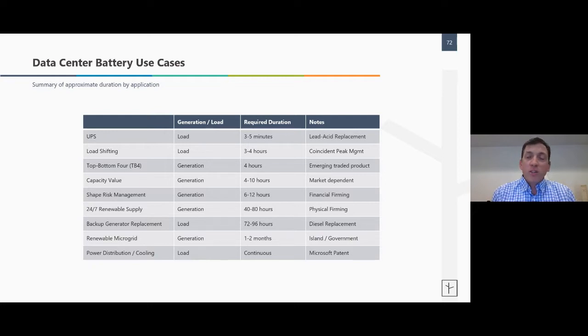Today, they generally keep 72 to 96 hours of diesel on site. Not the greenest application in the world. And when we're talking about very large data centers, the large ones of which are 300 to 500 megawatts, show me a jurisdiction that will permit enough tanks for enough diesel to carry 300 to 500 megawatts for 3 to 4 days. Especially in Europe, those sites do not actually exist. So there is an emerging need for a replacement for diesel and even natural gas.